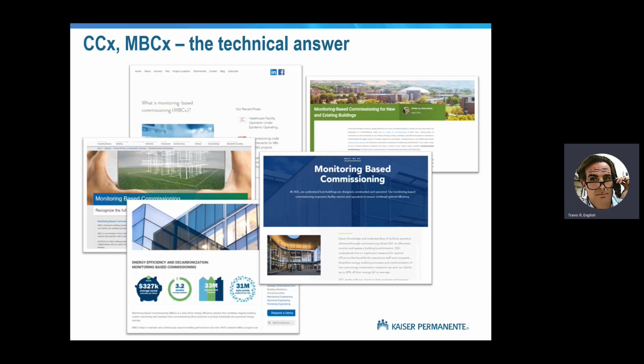Now, my second job here is to convince you that we can solve the accuracy problem. And a big tool in that toolkit is connected commissioning and monitoring-based commissioning packages. With connected commissioning, we're taking building system data and connecting it to cloud-based diagnostics and making that data available to a wider audience. DDC controls are not new. We've had them for 25 years, but the data has always been locked up at the building where we can't use it. So the game changer with connected commissioning systems is accessibility. With a connected commissioning system, the data from the building is on the cloud, which means that on day one, when the building opens, our design engineer can be looking at the data and the diagnostics from their house in their underwear.